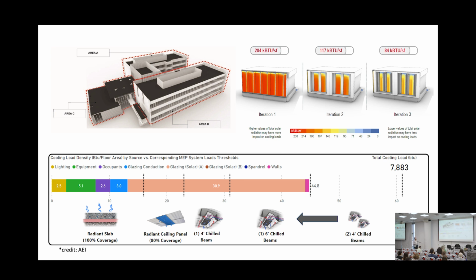And if health and wellness wasn't enough for a talking point, because of this analysis, because of that reduction in peak solar load, we were able to go from 2 chilled beams down to 1 chilled beam that was slightly larger. So this is a first cost savings — about $2 million in savings for your mechanical systems just through that focus on the facade.